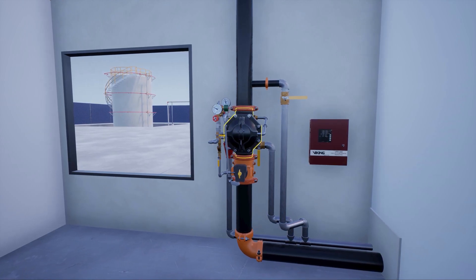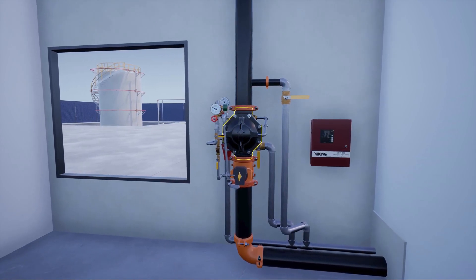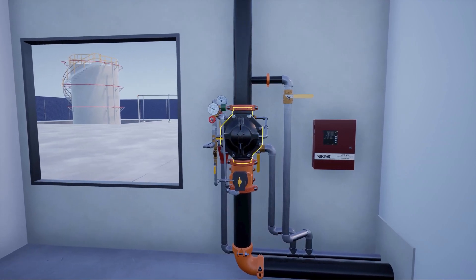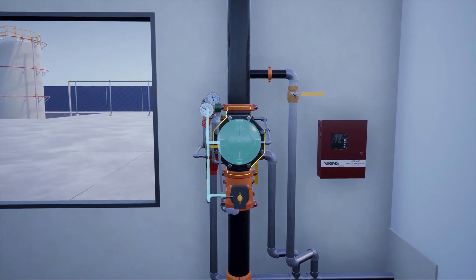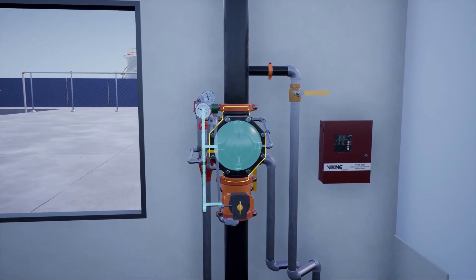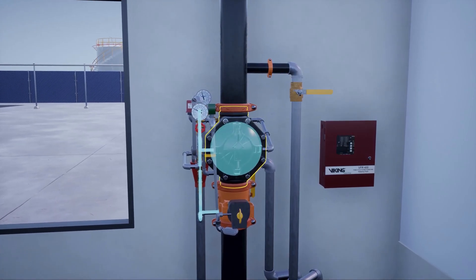The VXD deluge valve is a flood valve with only one moving mechanism. The valve is held closed by priming water pressure trapped in the priming chamber. This keeps the outlet chamber and the system piping empty.